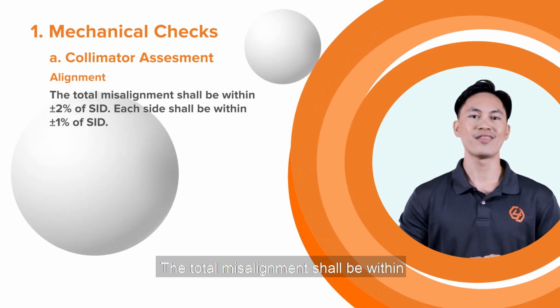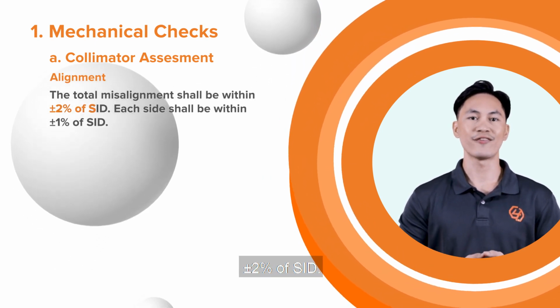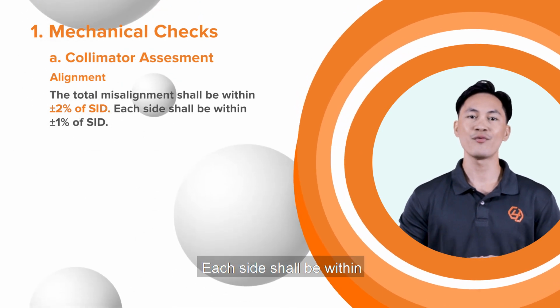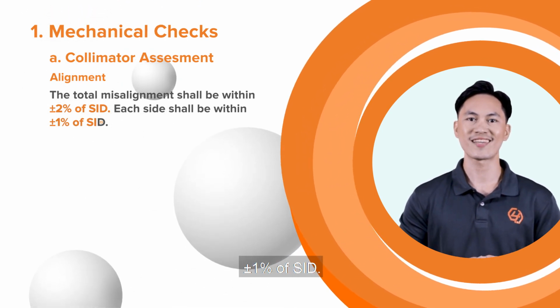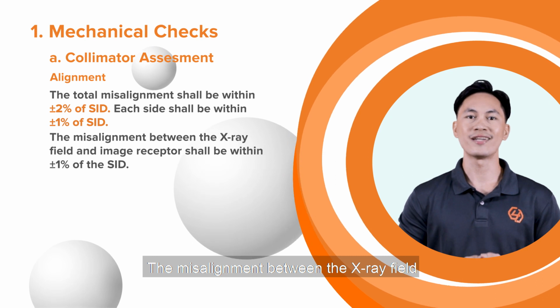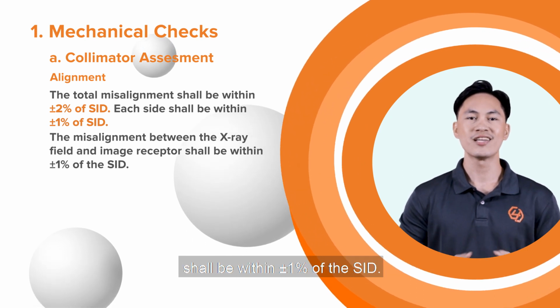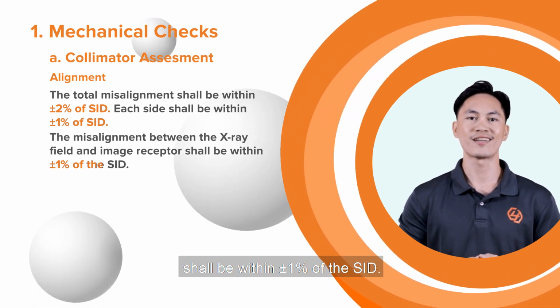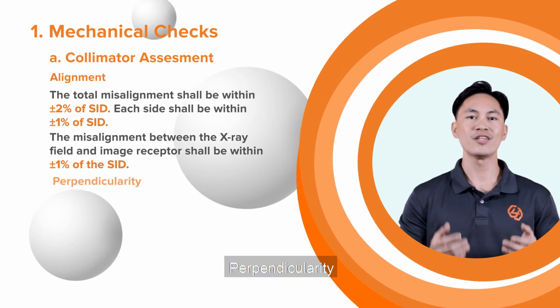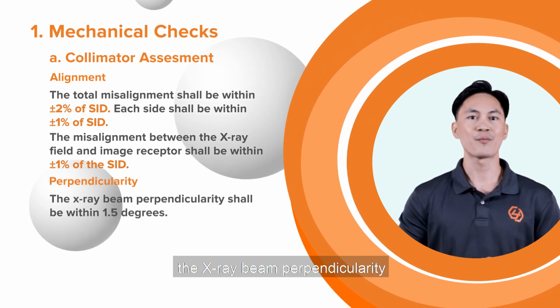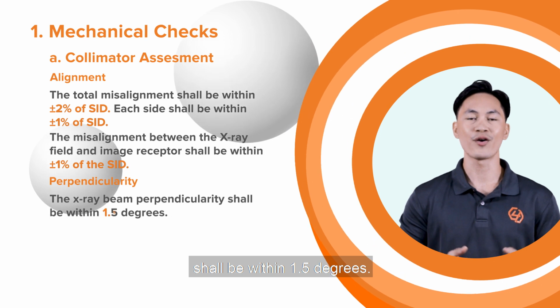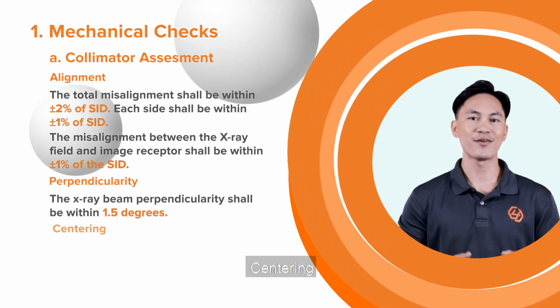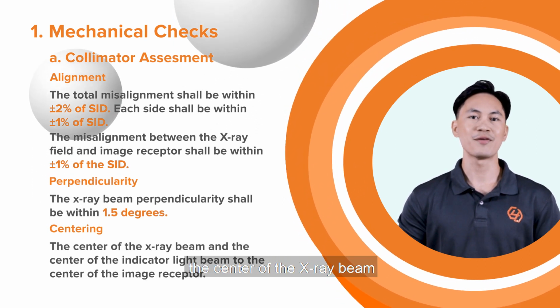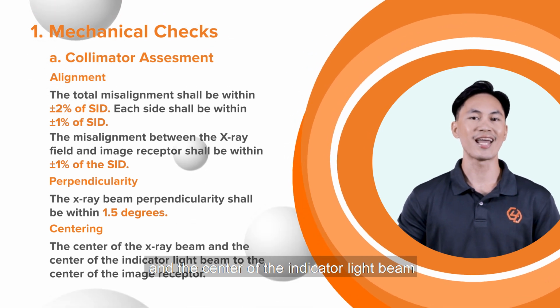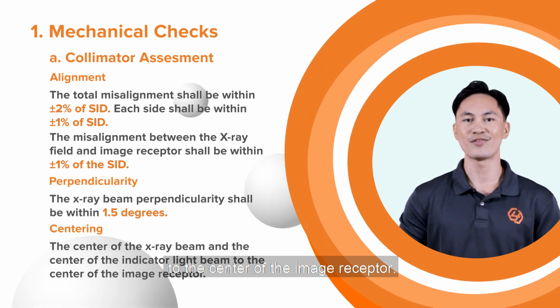Alignment. The total misalignment shall be within ±2% of SID. Each side shall be within ±1% of SID. The misalignment between the X-ray field and image receptor shall be within ±1% of the SID. Perpendicularity. The X-ray beam perpendicularity shall be within 1.5 degrees. Centering. The center of the X-ray beam and the center of the indicator light beam to the center of the image receptor.